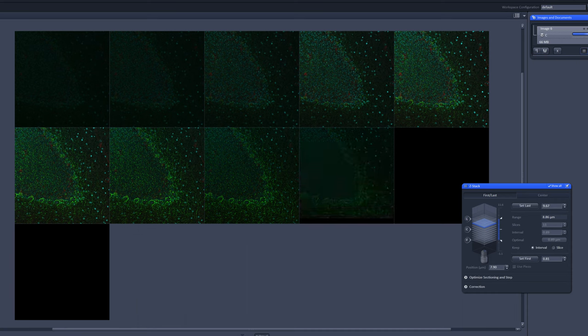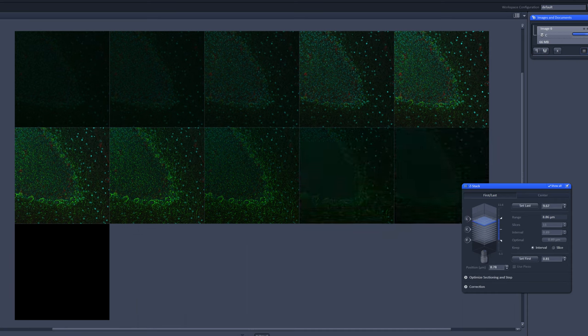We can gather further information from our specimen by scanning a three-dimensional dataset. 3D datasets, or Z-Stacks, are simply 2D scans collected at different focus positions throughout a three-dimensional structure. Confocal software can be set up to automatically collect a serial scan in Z by marking the top and bottom focus positions in your sample. The imaging software can then calculate the ideal number of slices to image based on your objective's resolution.